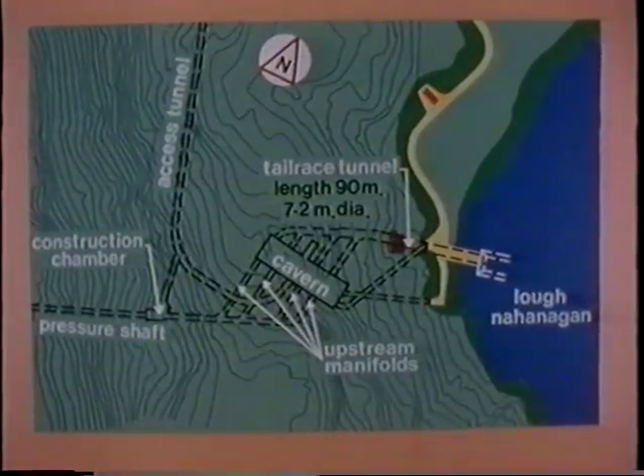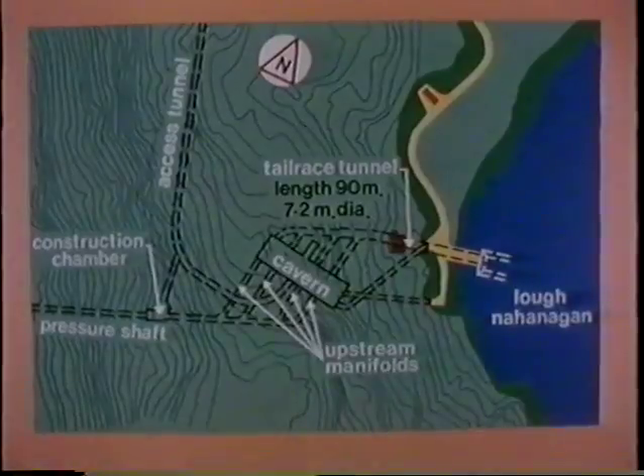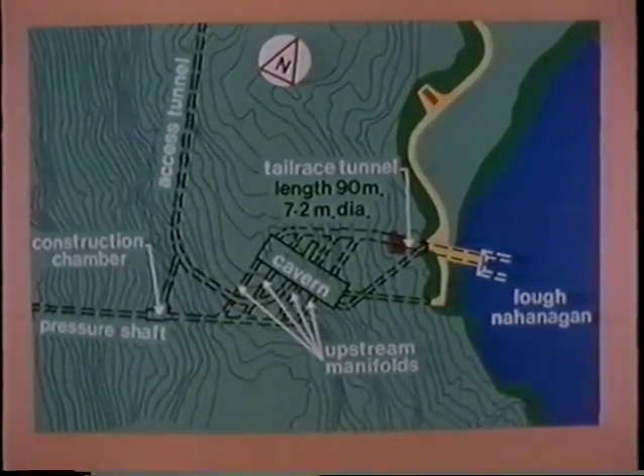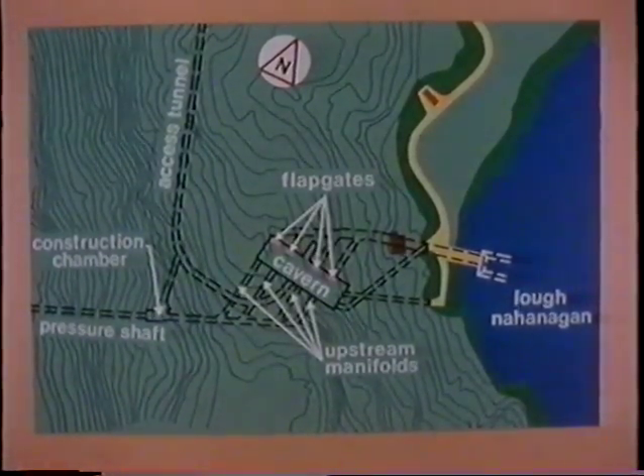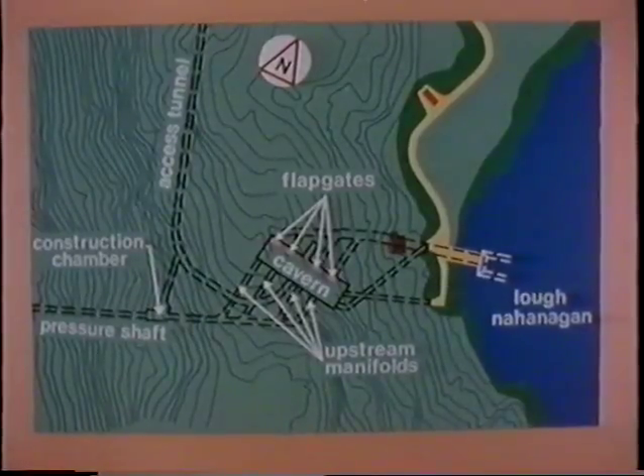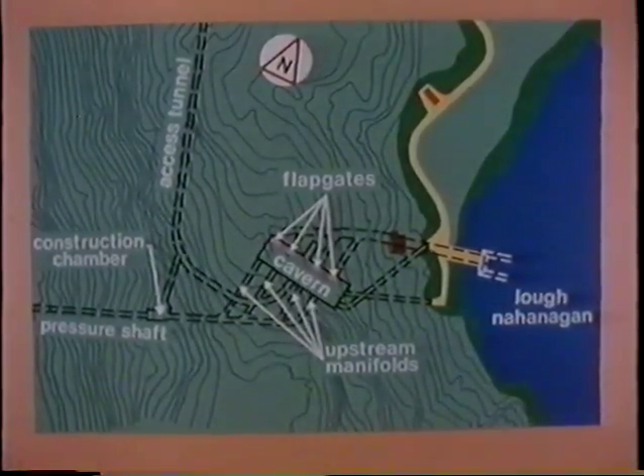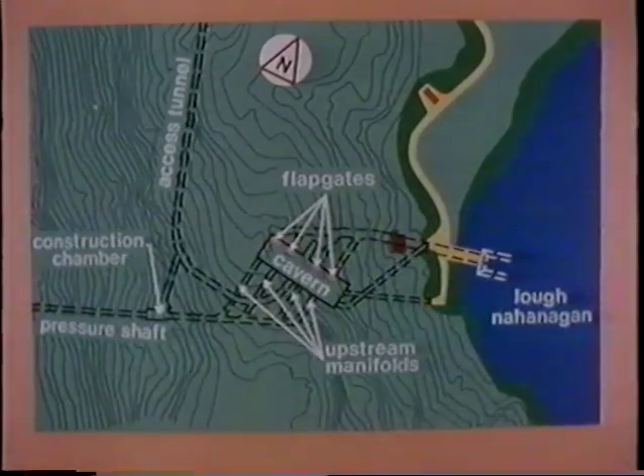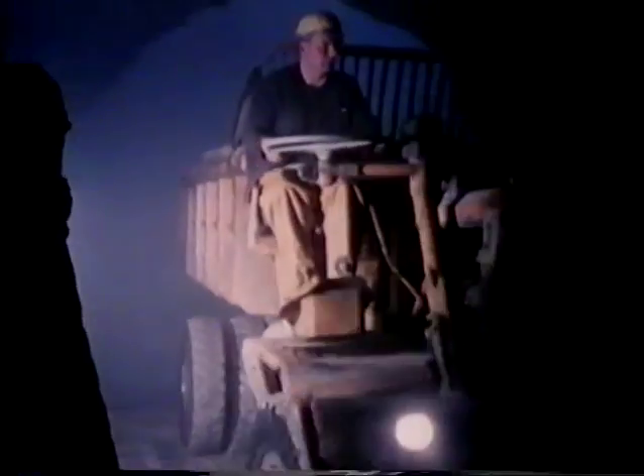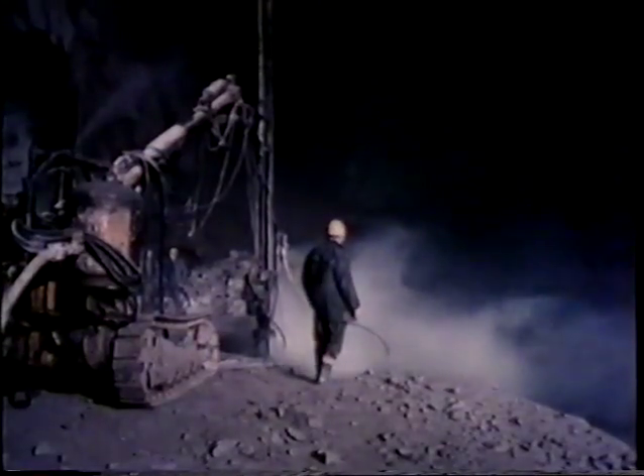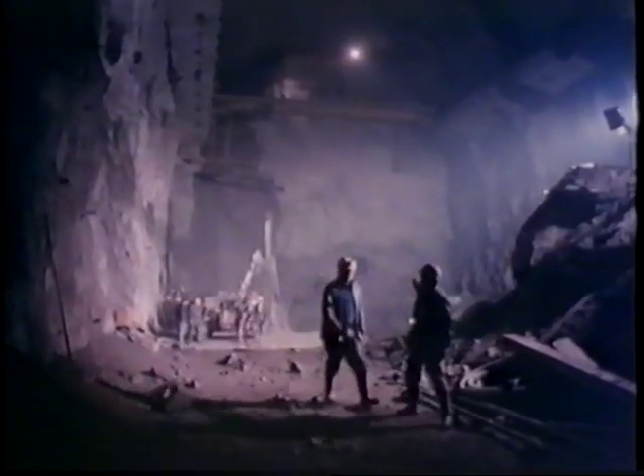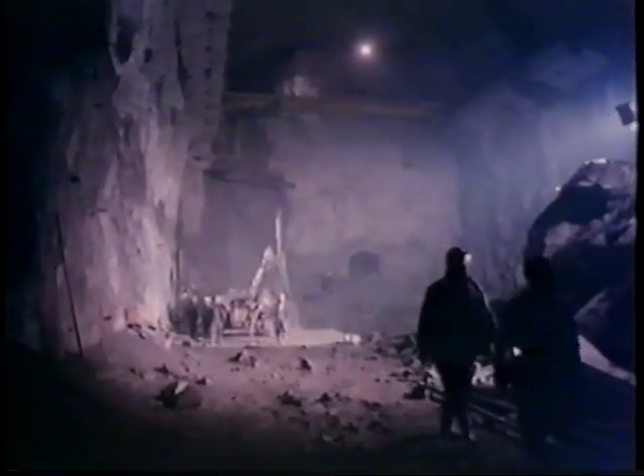The tail race tunnel is 90 meters long and 7.2 meters in diameter. Flap gates in the downstream manifolds can be lowered to cut off backflow from the lake in case of emergency. The size of the cavern required for the generating hall depends upon the type of plant which it must contain. Reversible pump turbine motor generators require very much less space than separate elements and are also much less expensive.